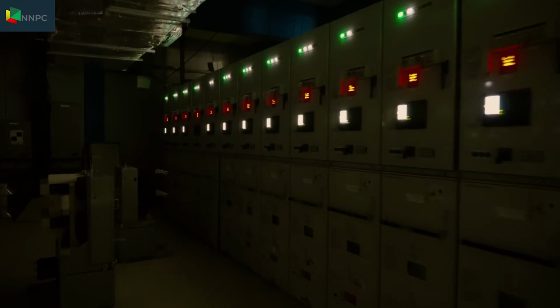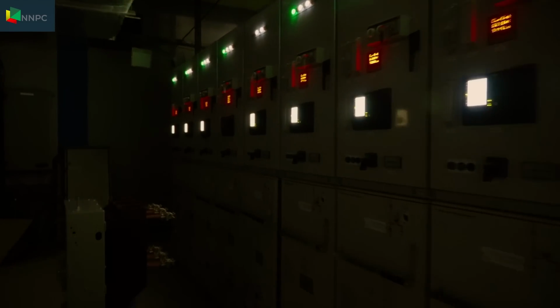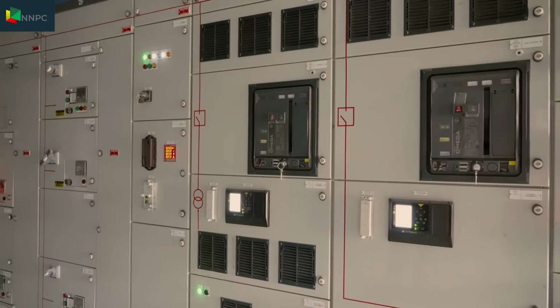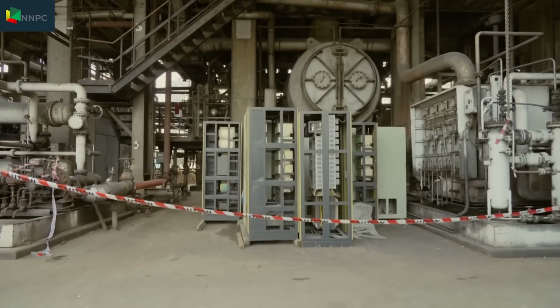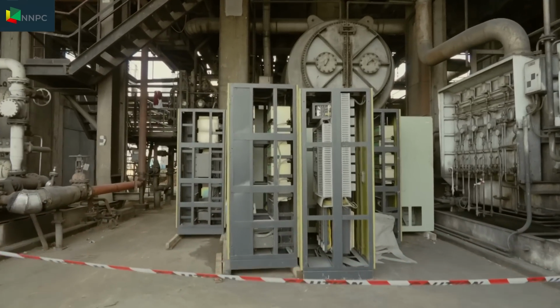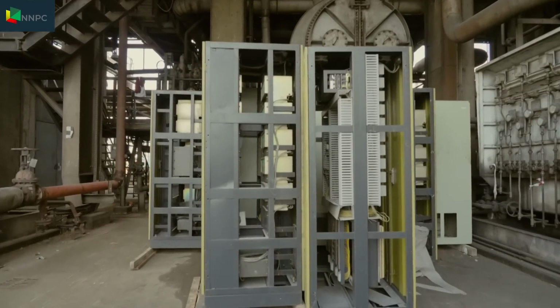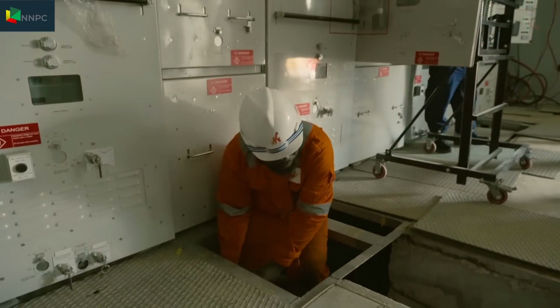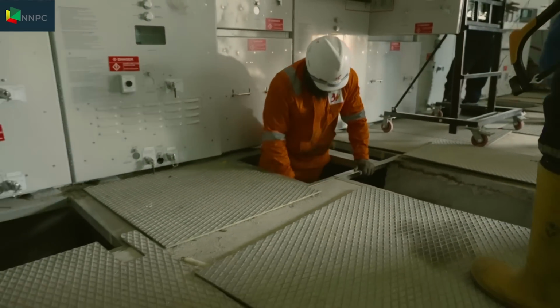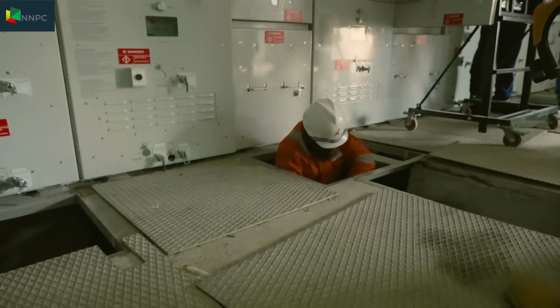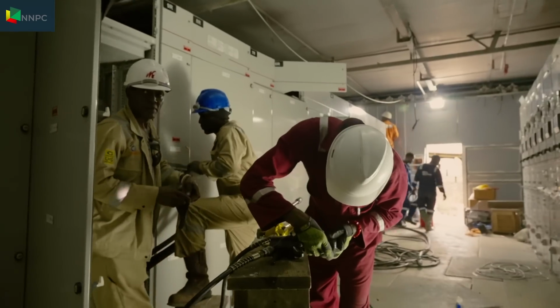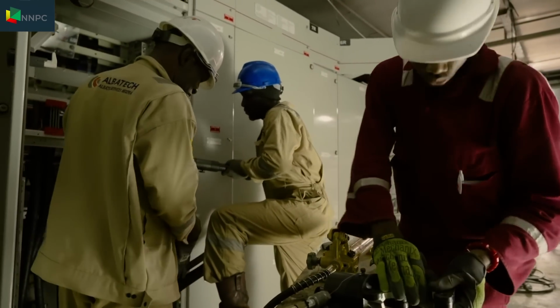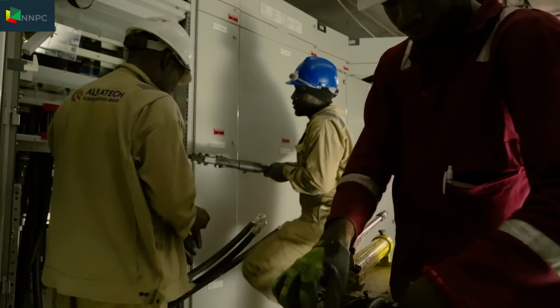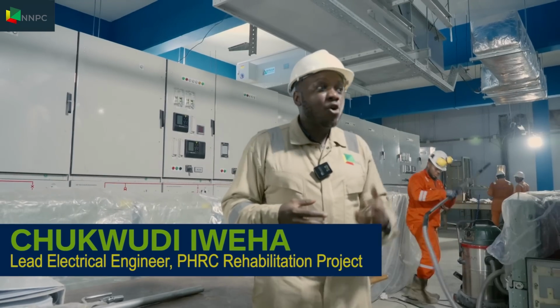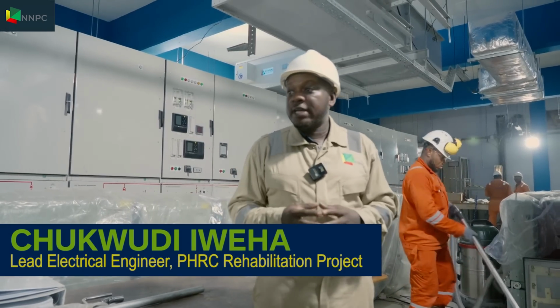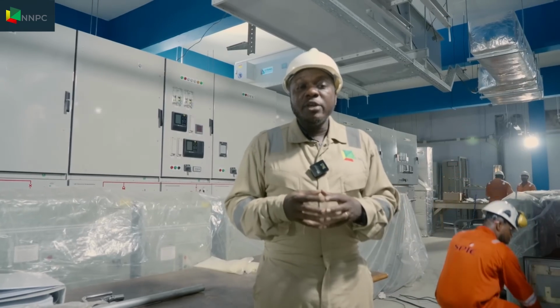It is a complete rehabilitation of all substations at the refinery and not a revamp or upgrade. Here lies old equipment that has served the substation for decades. Currently at the pre-commission stage, a total of 100 electrical staff worked on the installation of the switchgear panels. The good thing is it's been installed in Nigeria, majorly by Nigerians, under the good supervision of both the NETCO and the PHRC team, to make sure that they work efficiently and we minimize the errors.